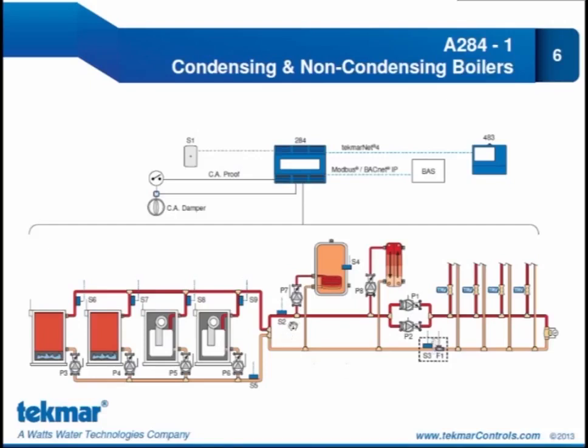If I have a flow sensor, a boiler supply sensor, and a boiler return sensor, then I can do an energy calculation. And that energy usage can also be communicated to the building automation system for remote monitoring. Other sensors on the system include a boiler inlet sensor, S5, and each of the boilers has its own boiler outlet sensor. And I can use that outlet sensor to set a boiler max temperature for each boiler, so that if the outlet temperature on a boiler exceeds the boiler max setting, the 284 will shut that boiler down.